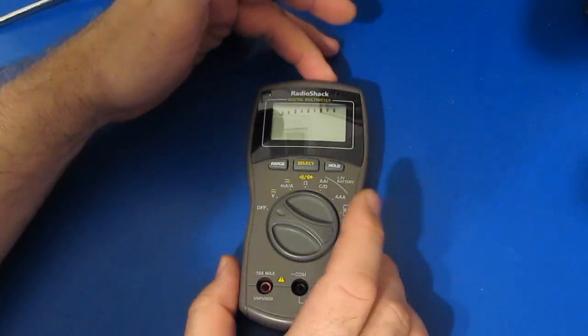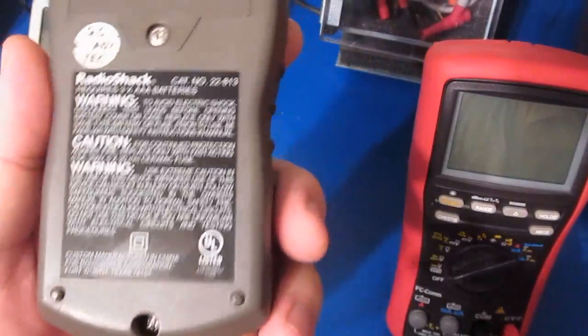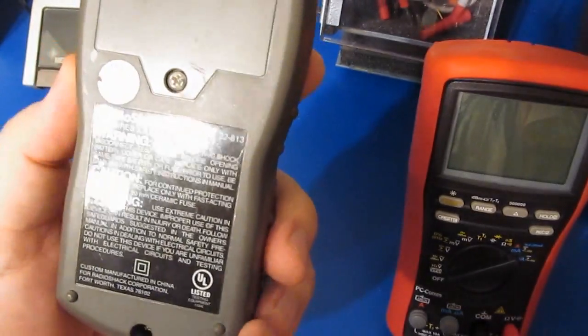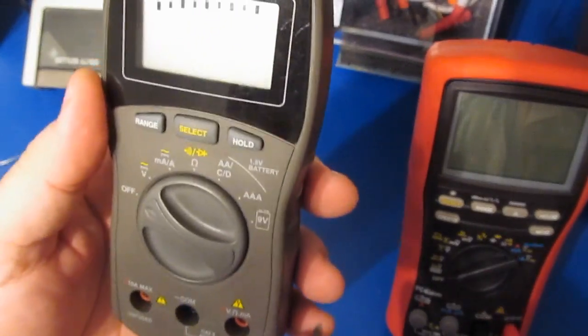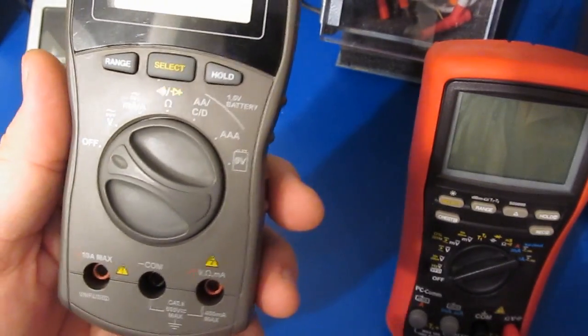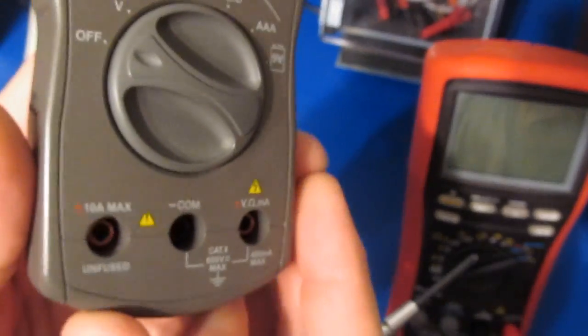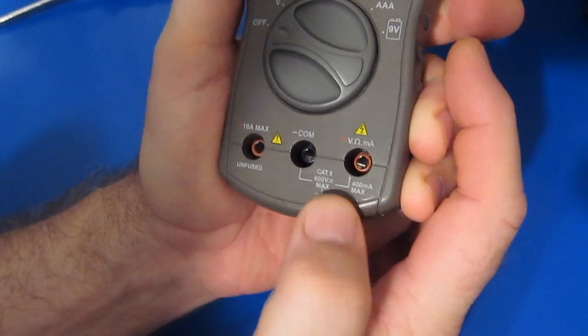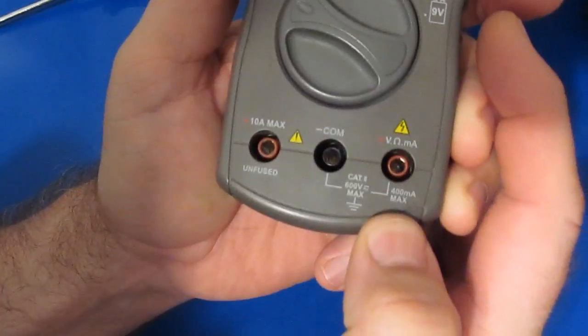I've gone through and functional tested it. We can see the meter is UL listed. Based on when this was built I don't know what standards this thing would actually meet, especially being able to have the unfused input like this. I don't think that would be allowed today by UL.